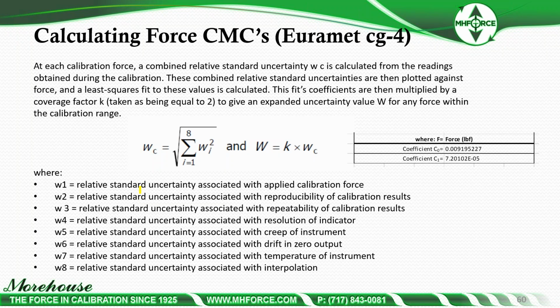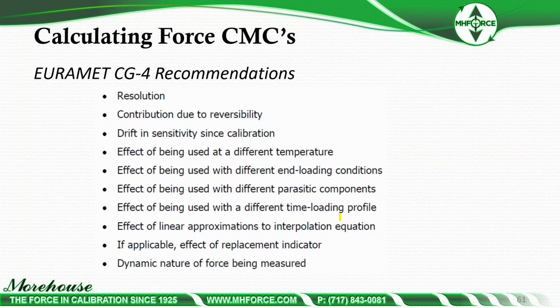All these, we give on our certificate an uncertainty equation. What you can do is you can take this equation and plug it into our Excel sheet, which I will talk to later. But EURAMET CG-4 is going to say resolution, contribution of all these, reversibility. What's interesting, and we didn't cover these, being used at different temperature, being used with different end loading conditions, effect of being used with different parasitic components. That bearing pad test is nice there. A different time loading profile.